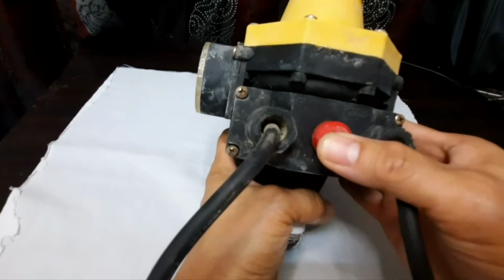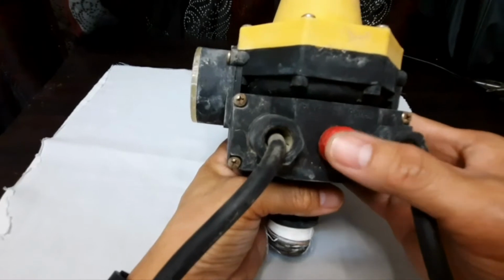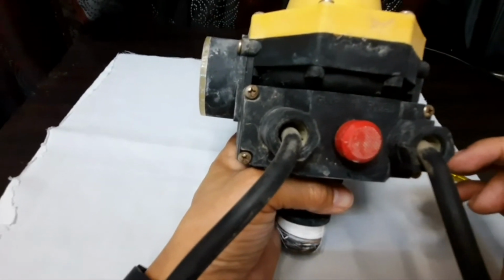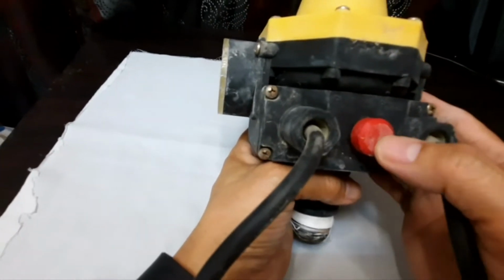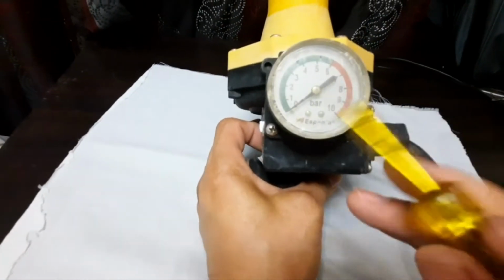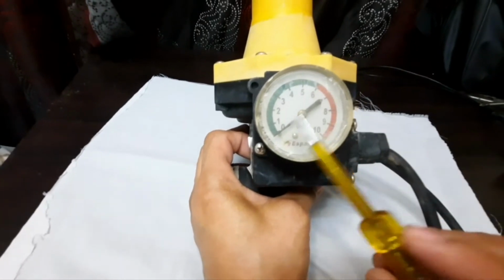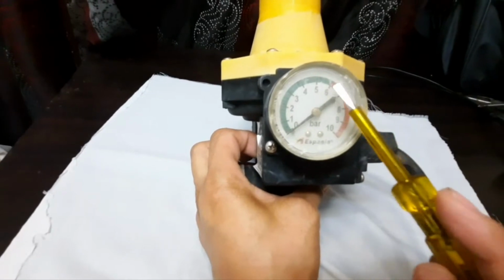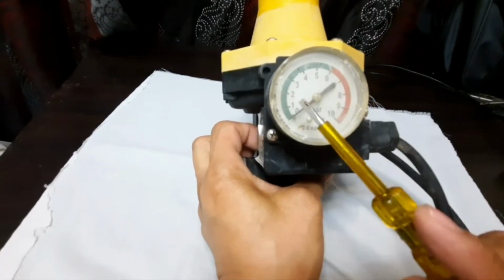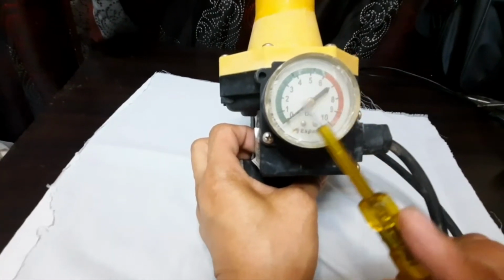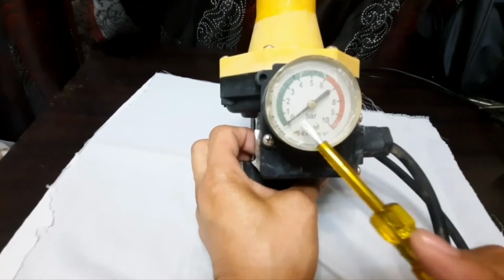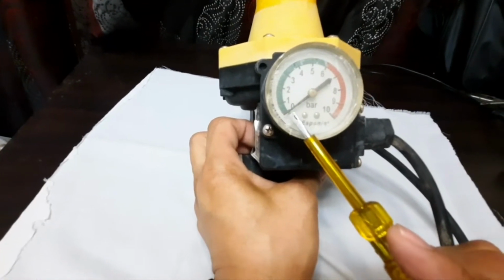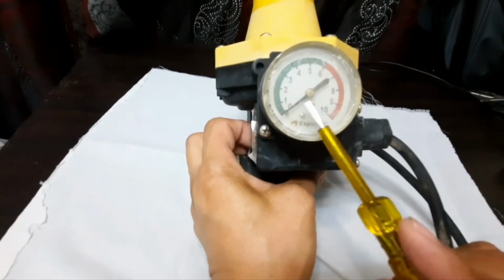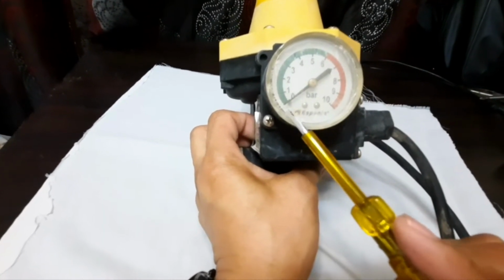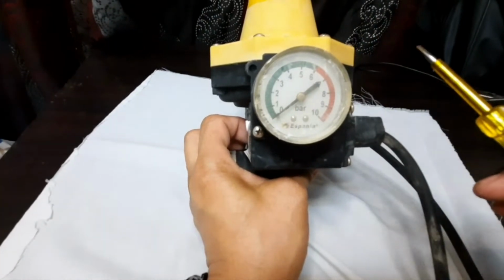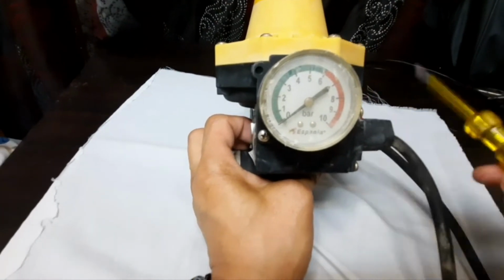So in case your pressure switch or the pump fails or stops due to lack of supply pressure, you can simply reset by pressing this switch. Okay, so as you see here, there is a green indication and red. So when the pressure builds up to 6 bar, or between 4 to 6 bar, this pressure switch will turn off. Okay, and if suppose the pressure from the supply is less than 1 bar, it will automatically turn off. So if there is no pressure from the supply line, water supply, this switch will deactivate the pump in order for it not to get damaged.